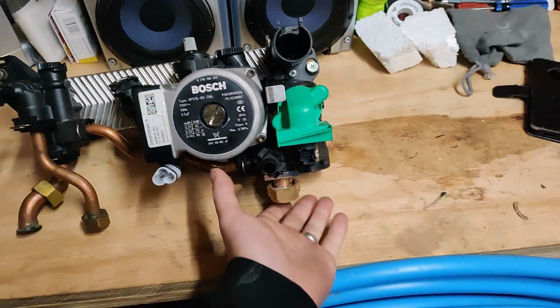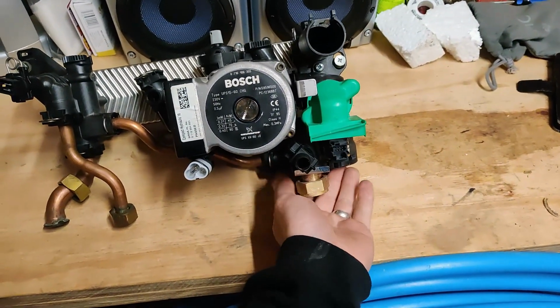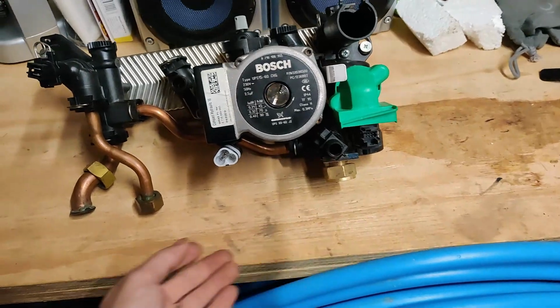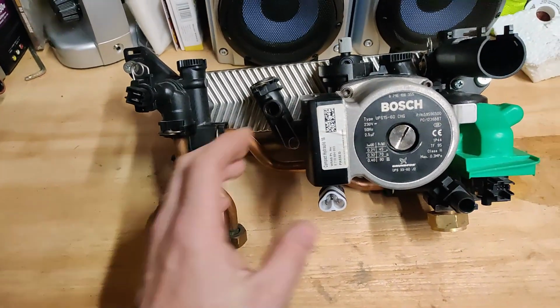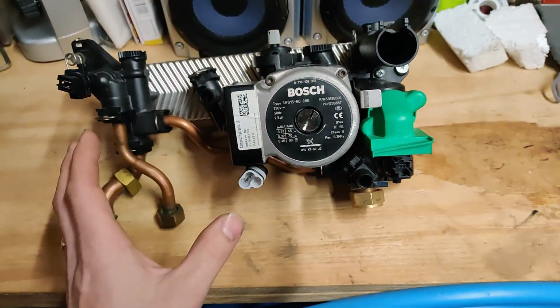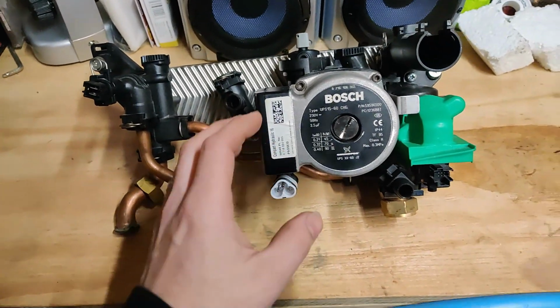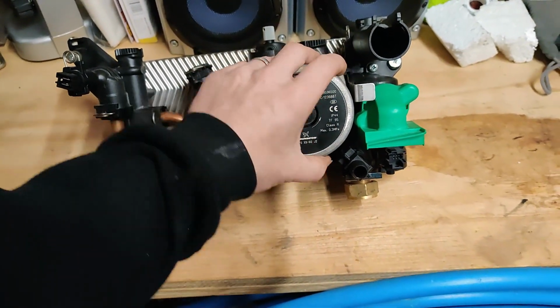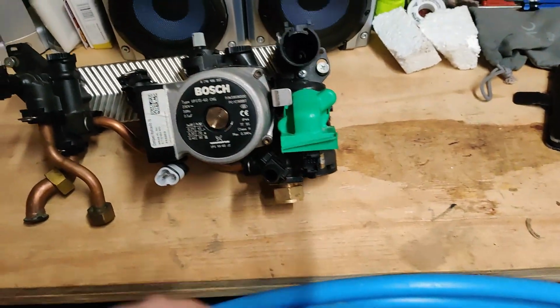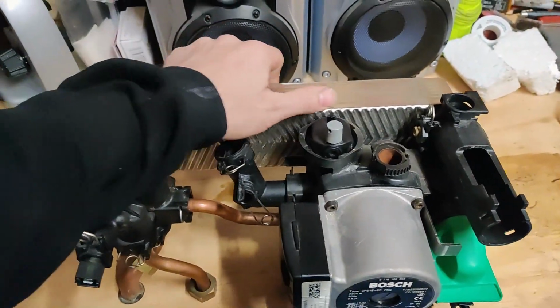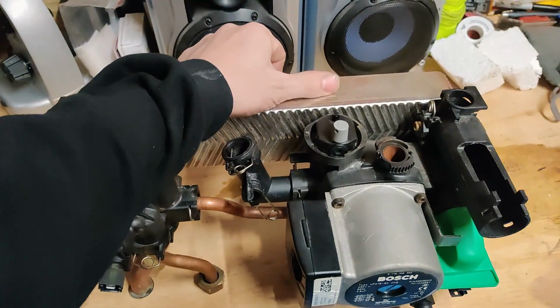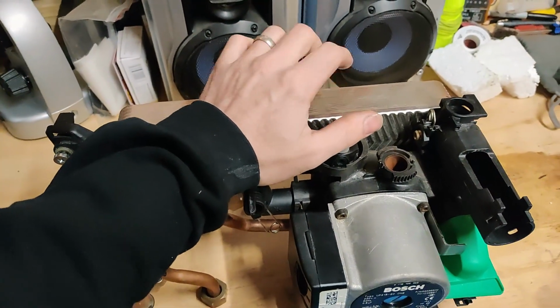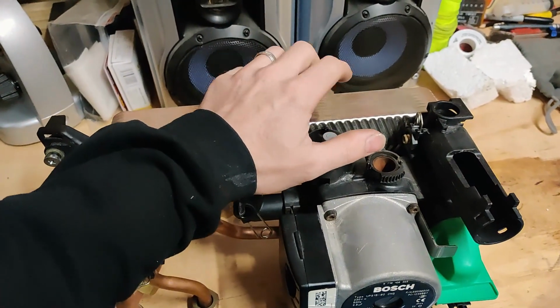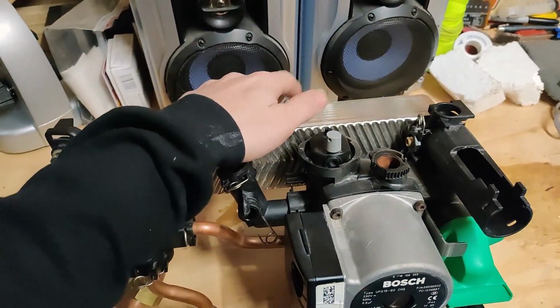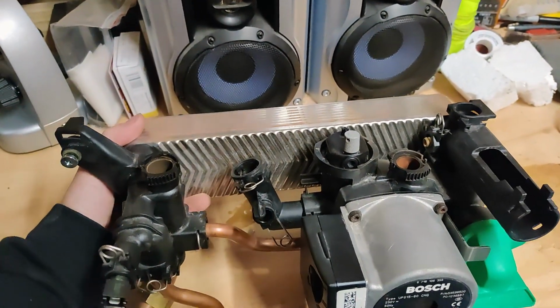This side here is your return side, and this side here is the flow side. I've been refurbishing this, put brand new seals in it and everything, lubed it all up. I've renewed this pump motor. I've cleaned all this plate heat exchanger out, because what tends to happen with these is they get blocked up over a period of time, just with sludge from your central heating system and stuff like that, and they get blocked.